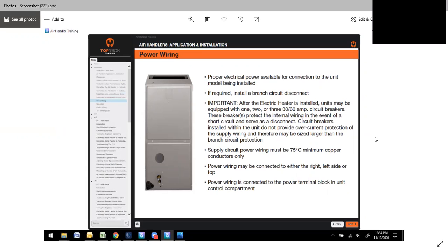Power wiring, like I say, generally, what we see is the 208, 230 models. So you've got to make sure that proper electrical power is available for connection to this unit. If required, install a branch circuit disconnect. It is important to have the safety disconnect handy. Important, after the heater is installed, electric heat units may be equipped with 1, 2, or 3 30 or 60 amp circuit breakers. These breakers protect the internal wiring in the event of a short circuit and serve as a disconnect. So it's basically a double service. They will protect the unit, but they'll also serve as a safety disconnect.